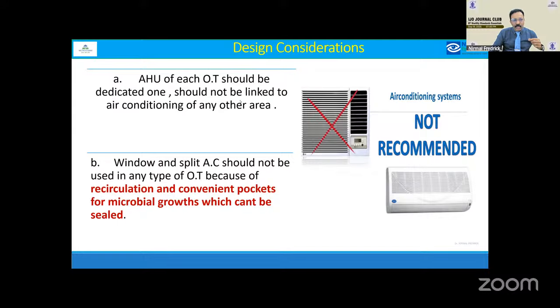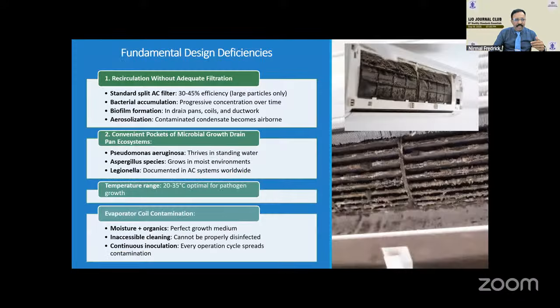This is why AHU should be a dedicated system, and window or split AC should not be used in any type of OT, because of recirculation and convenient pockets for microbial growth that can't be sealed or accessed by human hand. This is how some ACs look during our NABH inspection, showing fundamental design deficiencies in split ACs.